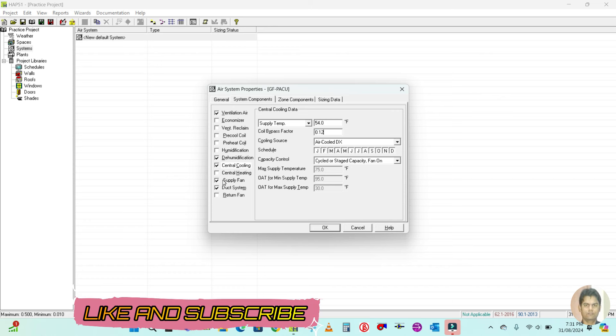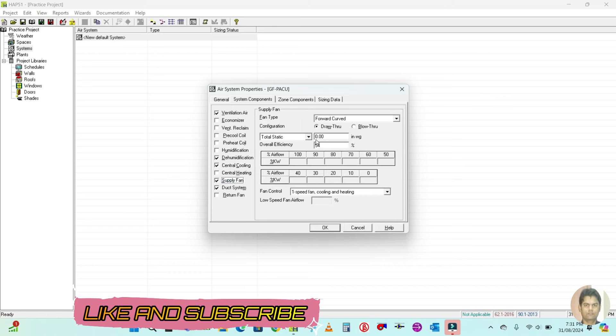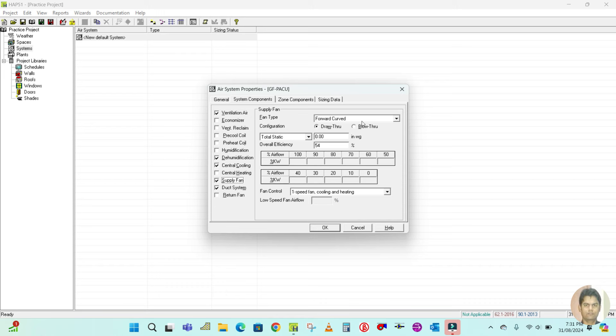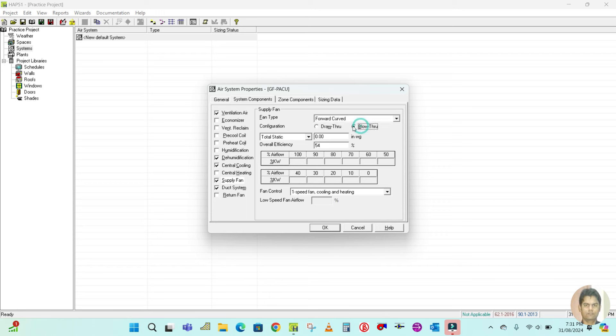Then go to the system tab. Here you can see dehumidification required — whatever is required in your project you have to select this. In our case, dehumidification is required, so it should be 50 to 60 percent — I'm going to keep it at 50 percent. Central cooling should be 54 to 56 degrees Fahrenheit, while bypass factor is 12 percent.